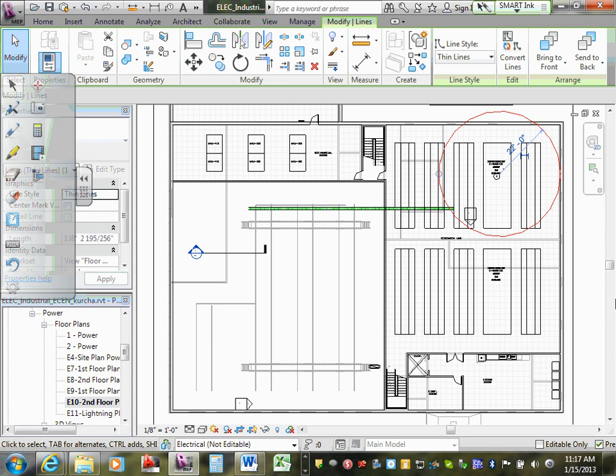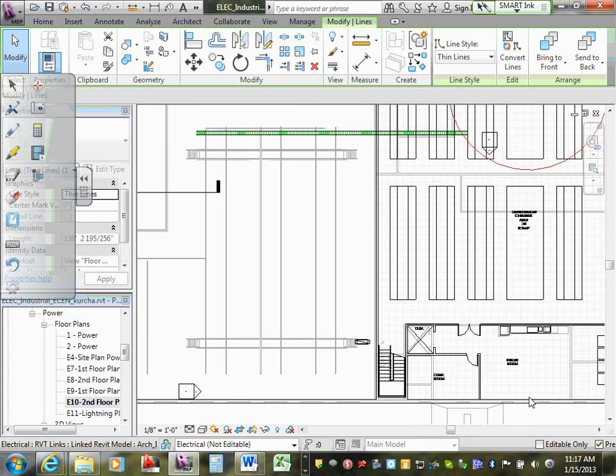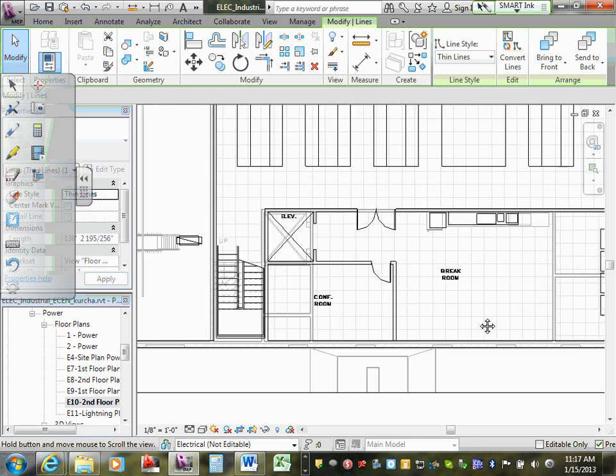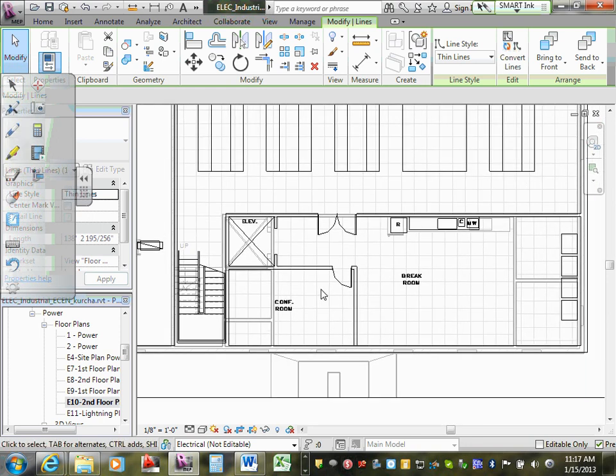Again, we had sounders in there. You're going to have an interconnected conference room and break room. You're going to have strobes, and that's just a visual. In a conference room, we try not to put horn strobes in, just because of the small spacing. If you're looking at a voice system, you want to put a speaker strobe in them to get that audio notification in there. But with a strobe in there, they'll be able to see it just fine.